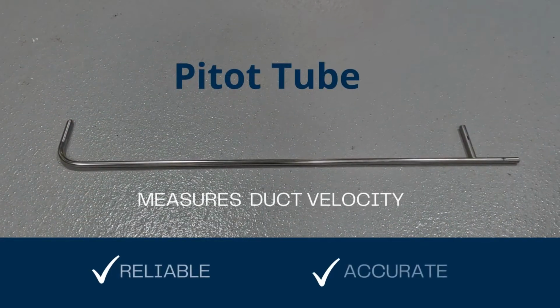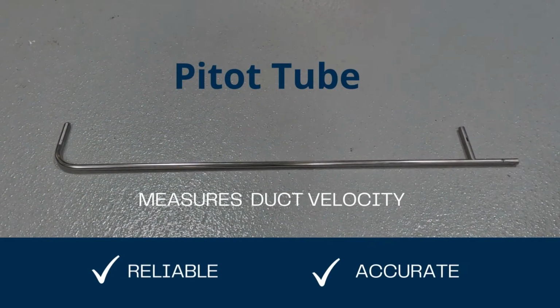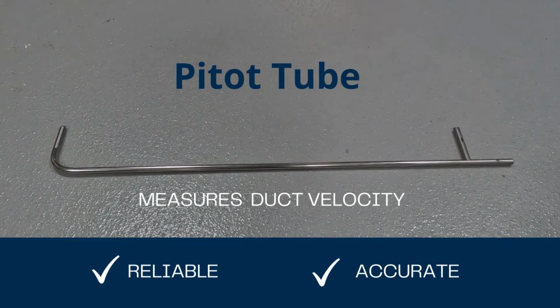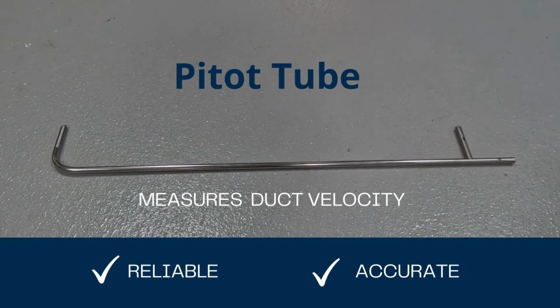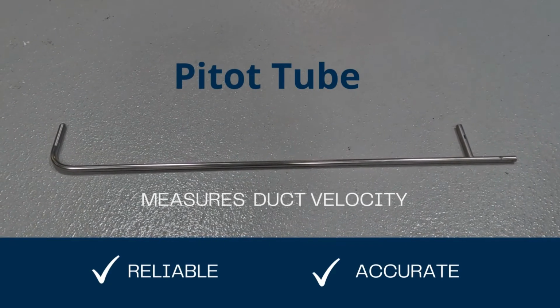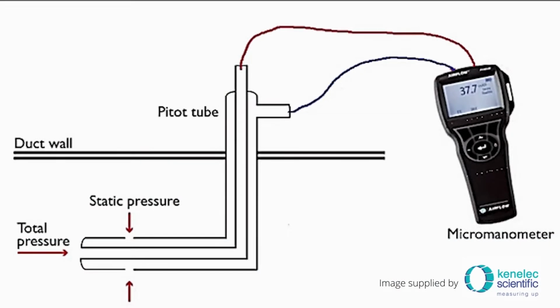Although there are numerous items that can be used to measure velocity in a duct, such as a velocity probe or a hot wire anemometer, a pitot tube is regarded as the most accurate. A pitot tube works by measuring the difference between total pressure and static pressure. Total pressure is the force pushing the air down the duct. Static pressure is the force pushing the duct outwards. The difference between total pressure and static pressure is expressed as velocity pressure. A typical micromanometer then converts this to velocity.